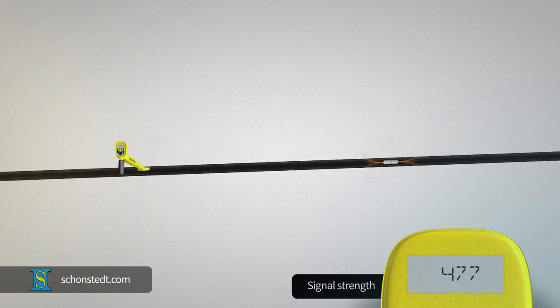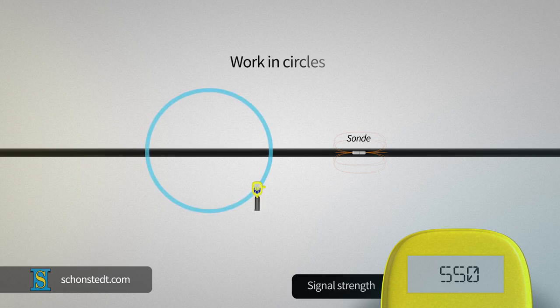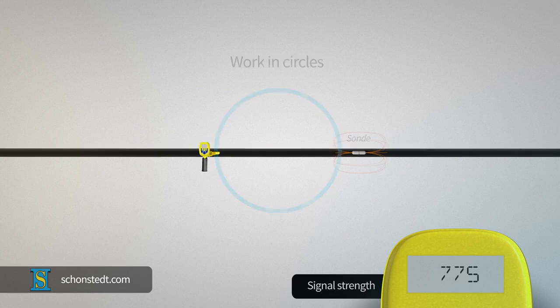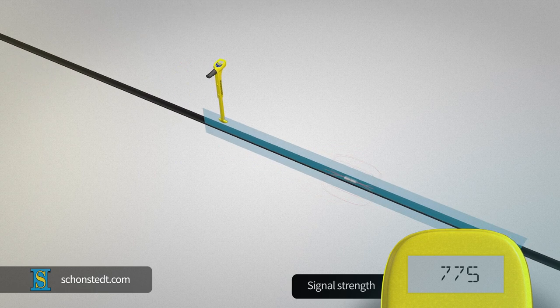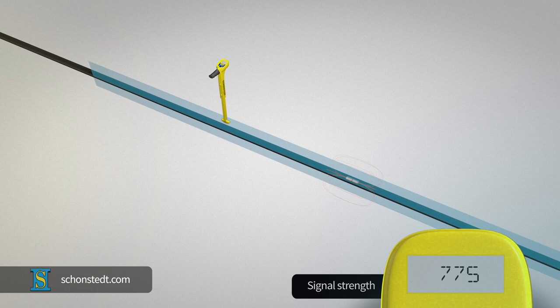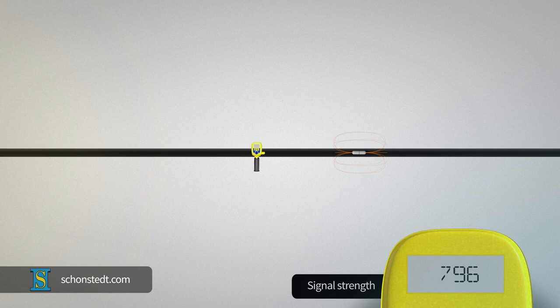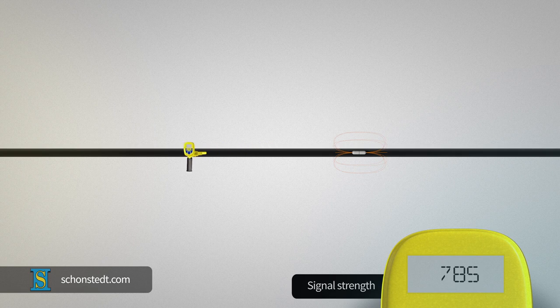To approach the sonde from a distance, it is best to work in circles while trying to determine where in the circle the signal is stronger. At that point, the sonde axis and the sensor axis are on the same plane.